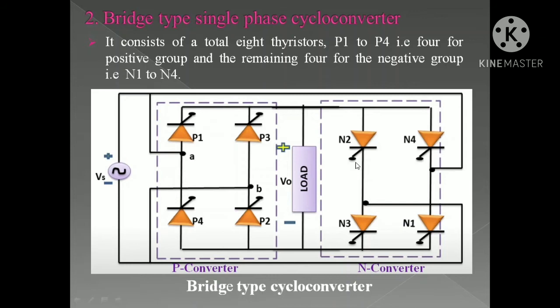The positively connected thyristors are called the P converter and the reversely connected thyristor bridge is called the N converter. The P converter thyristors are triggered so that the load keeps getting positive voltage, and the N converter thyristors are triggered so that you always get a negative voltage envelope at the load. It all depends on how you trigger the P converter bridge and N converter bridge.